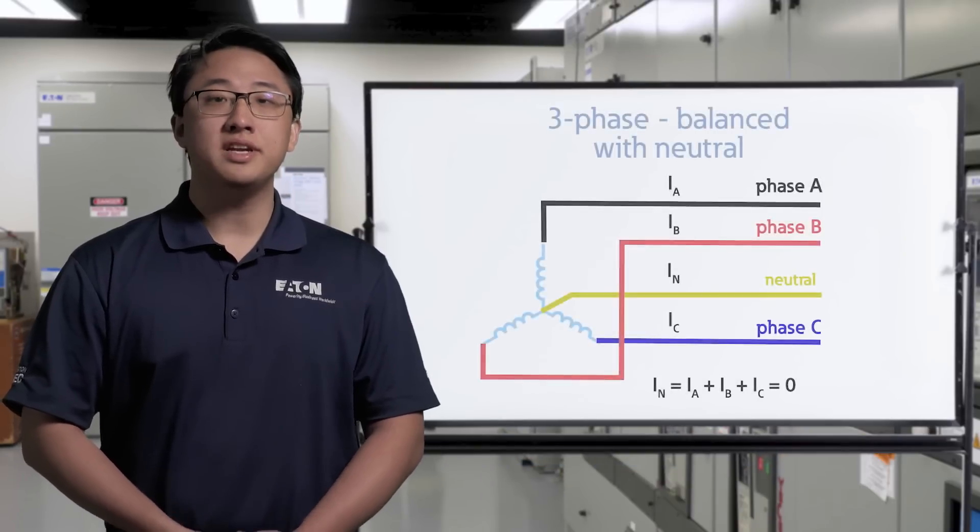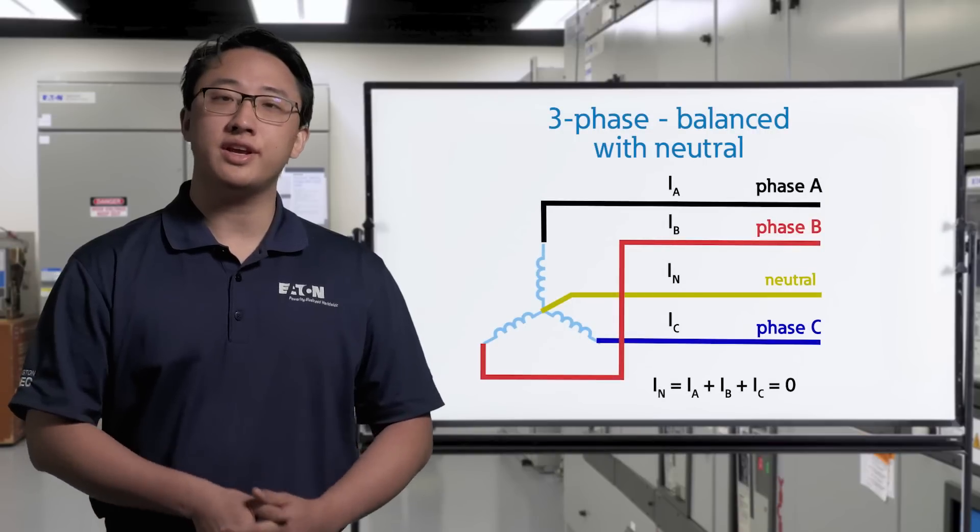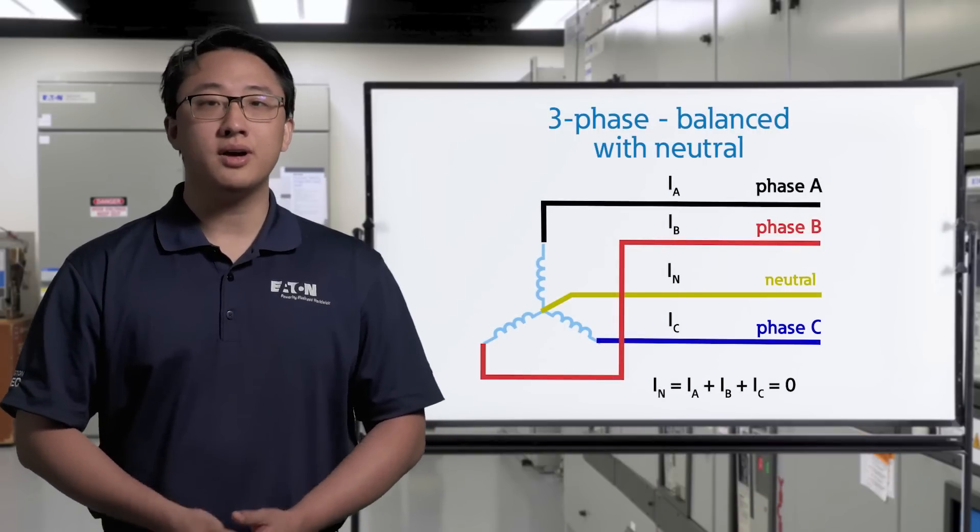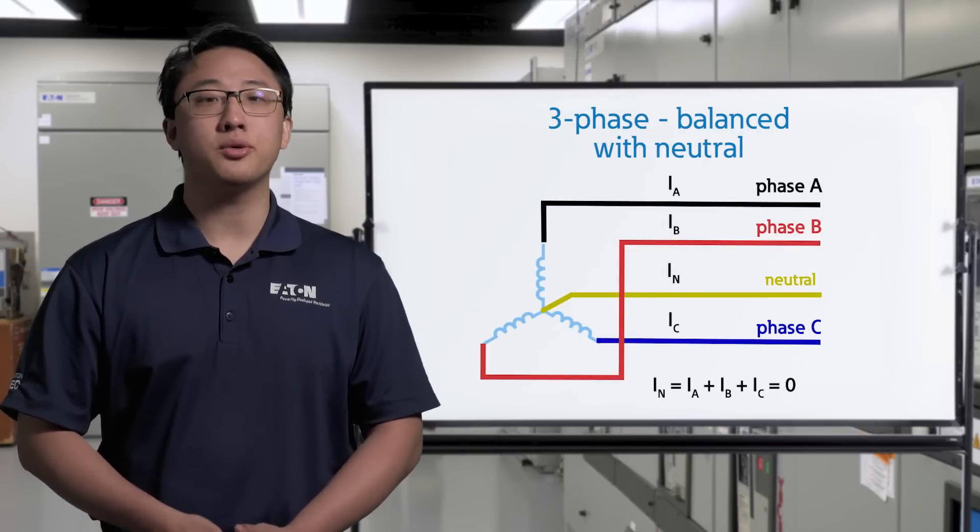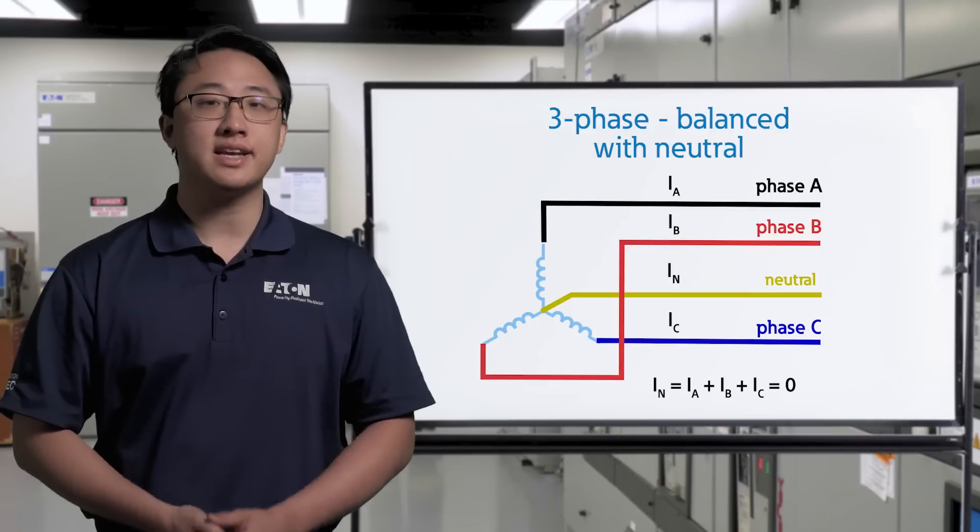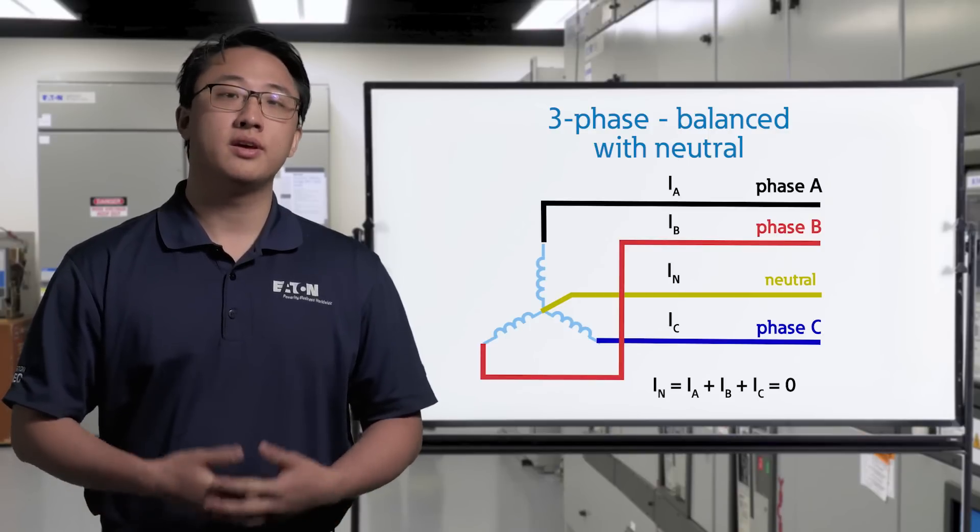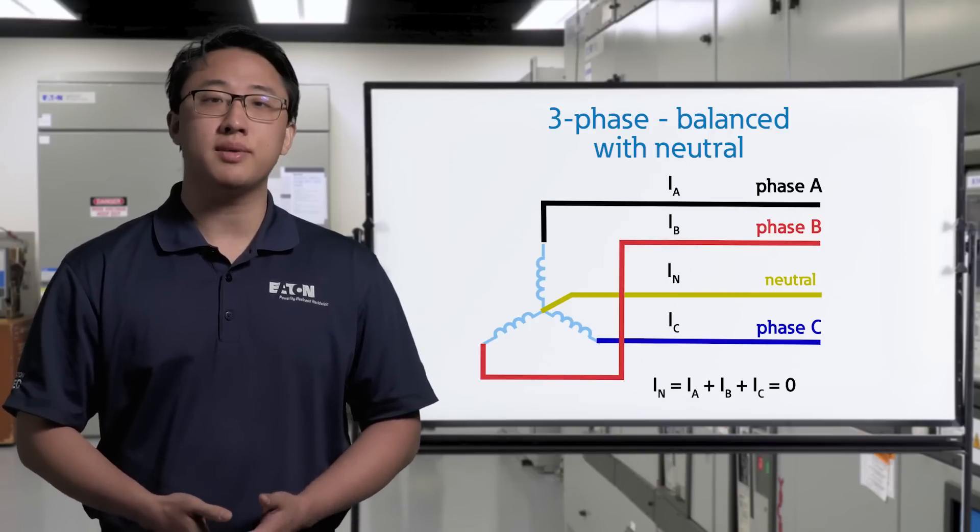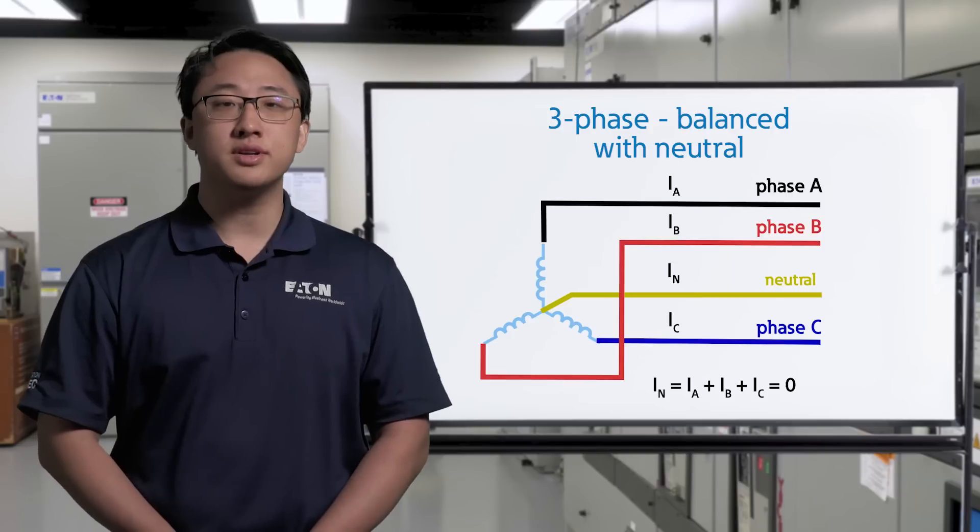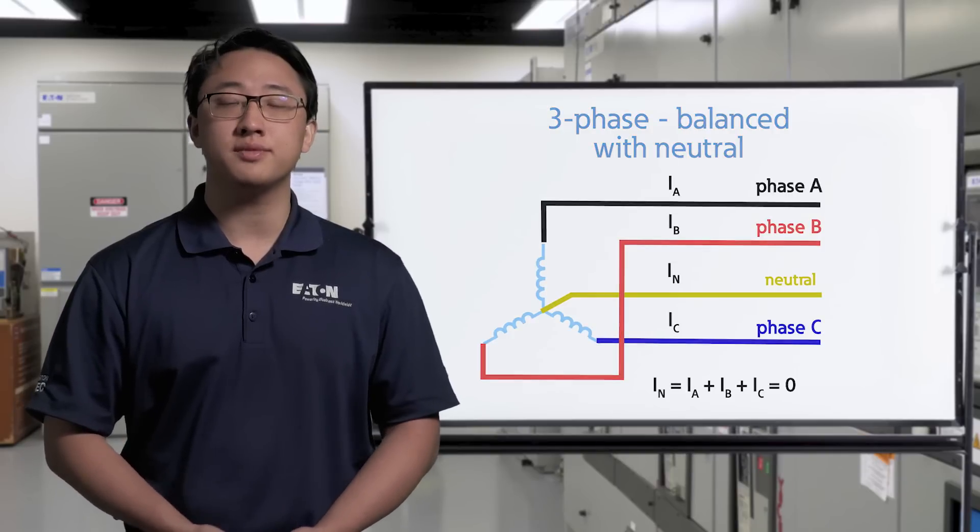To actively balance the system, we need to design for equal loading on each leg of the transformer. This will help transmit power much more efficiently and lower excess heat in the system, extending the life of the transformer. Most three-phase loads will draw even amounts of current per phase, so it's mostly single-phase loads on the three-phase system that need to be considered.